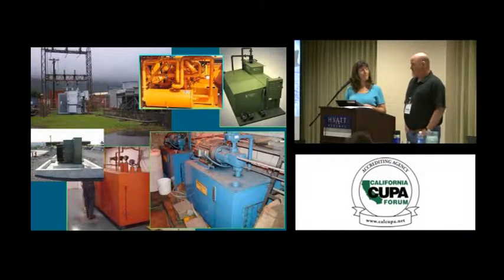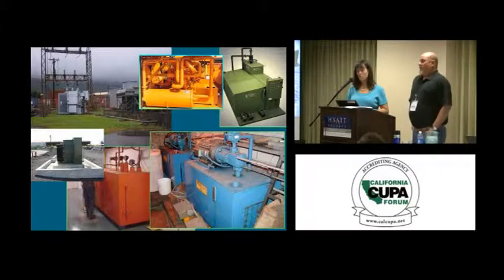Well, you certainly can consider walls and solid floor and the way that the area would provide containment to determine whether it's adequate. Okay, so it's a reservoir system, the oil's going in and out. Each reservoir is right at the 55-gallon amount. If the reservoir failed and the fluid hit the ground, could it flow under the door? Yeah. And where would it go then? Just into other rooms inside the building. Right. So really, that capacity, 55 gallons, if it's going to go out the door there, but it's not going to have enough volume to actually get out of the building and into a drainage course, you can claim that as general containment, certainly. As an inspector, I would take a look and say, well, if you have 55 gallons and it's going to fillet out into the next room, could it get out of the building and go somewhere? Then probably not.